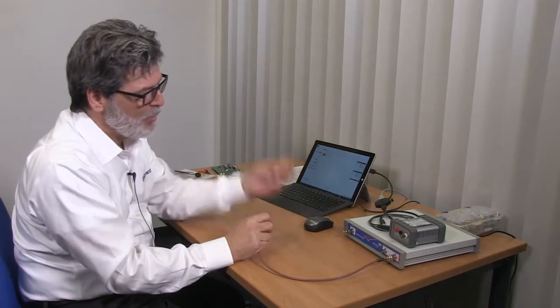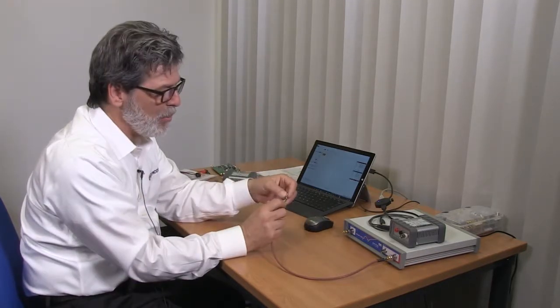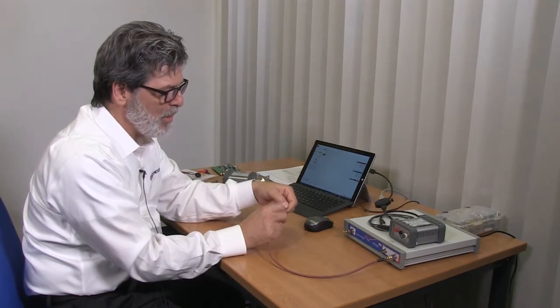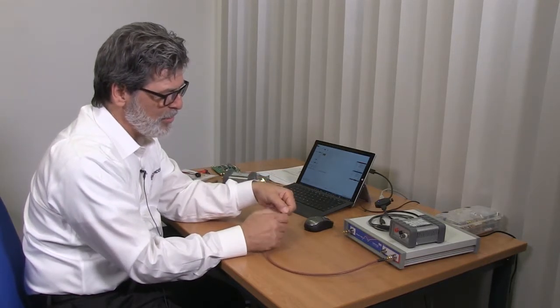We have a cable already connected to channel 2. We're going to start just by measuring something that we know. That's something that I always recommend. Every time you set up a new setup, you should measure something that you know the answer to.